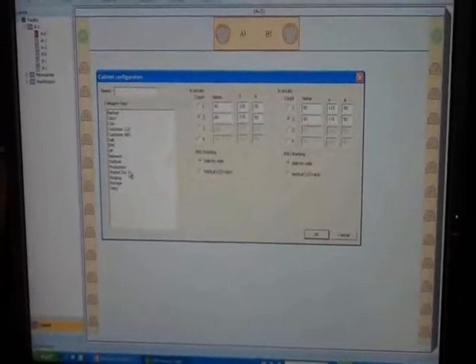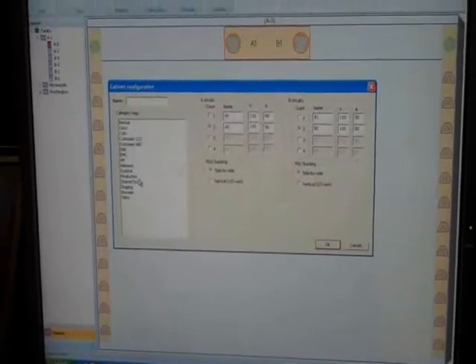The tags are customer definable. Basically what a tag is, is a way to aggregate power consumption data. So if you're a hosting company as an example and you want to be able to bill power consumption back to your customers, you can tag all of the assets associated with that customer across multiple facilities with their name, and our software will automatically aggregate the power consumption costs for that customer.